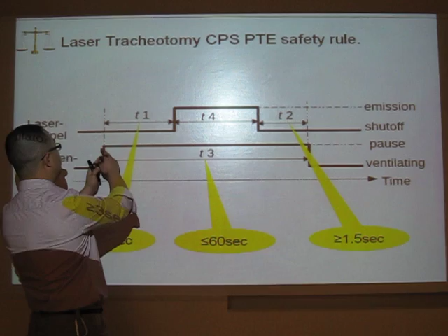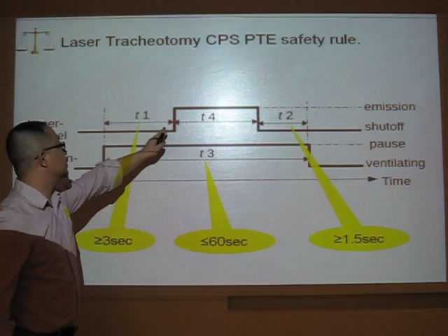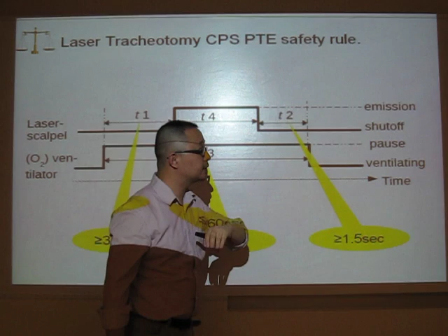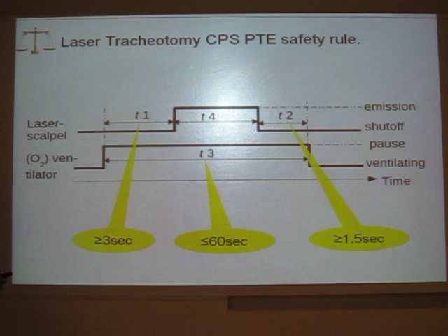Also, after you have paused the ventilator, we cannot immediately shoot laser. We must wait for a minimal time interval, 3 seconds, before we can shoot laser. Same thing, after we have stopped shooting laser, we must wait for at least 1.5 seconds before we can resume the ventilation of oxygen. So this means that we can apply our aforementioned leasing design pattern to guarantee the PTE safety rule in the wireless CPS of laser tracheotomy.